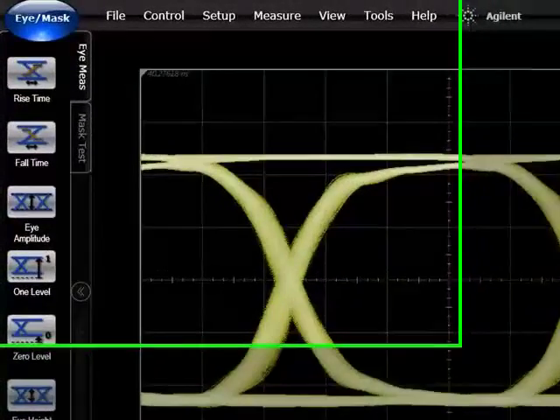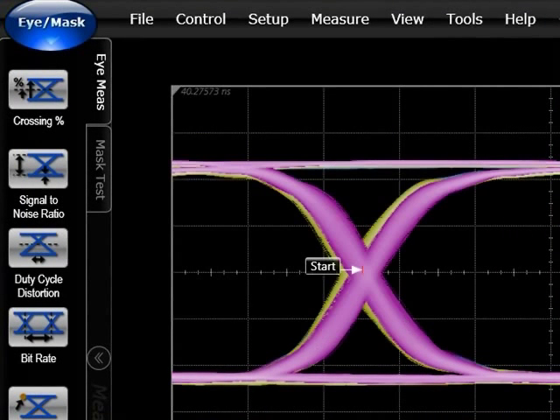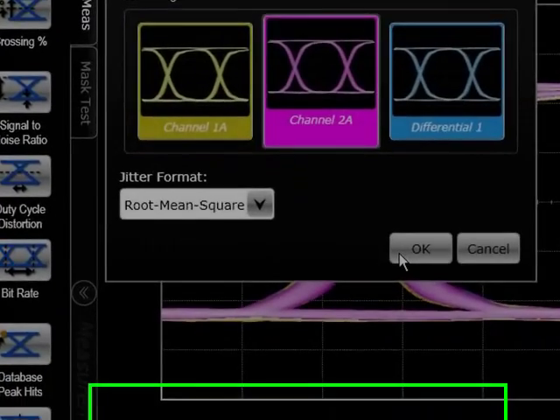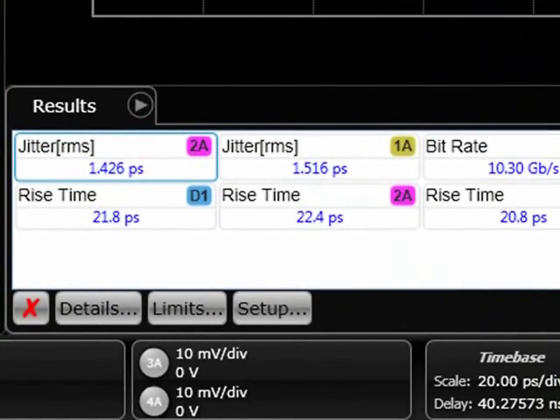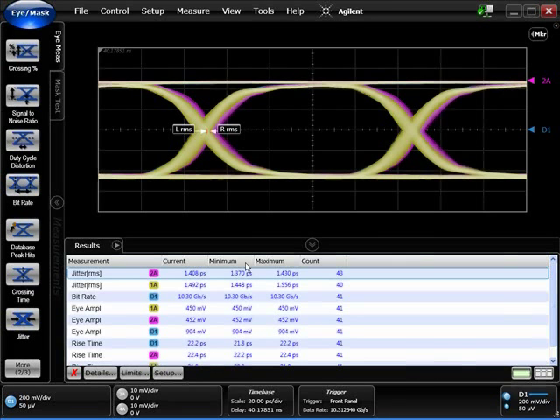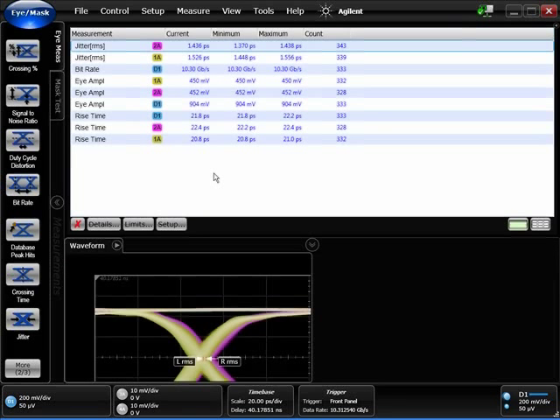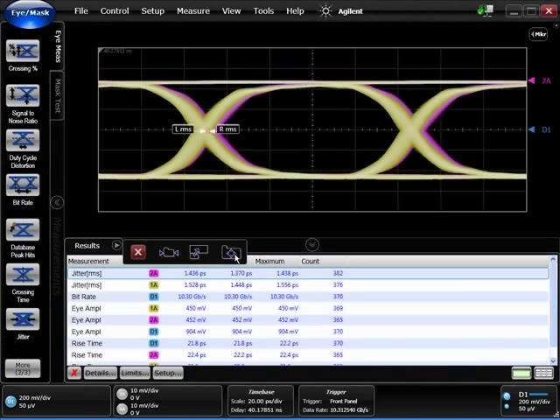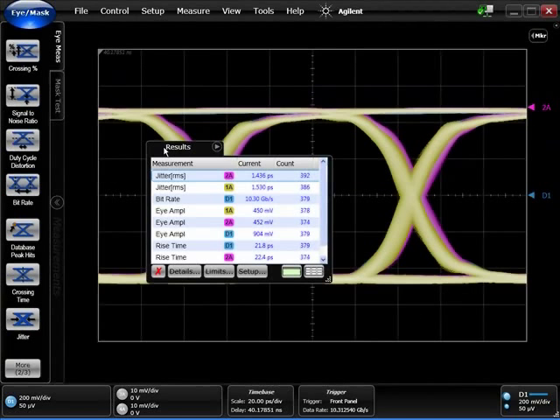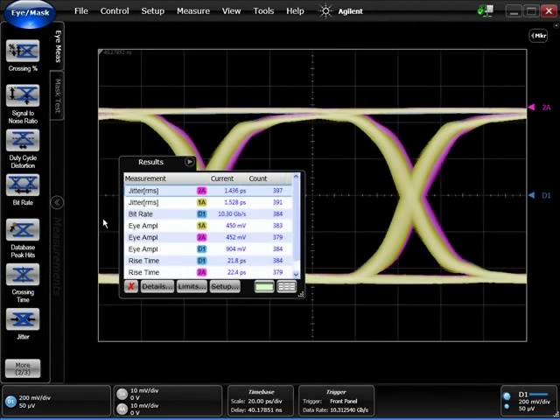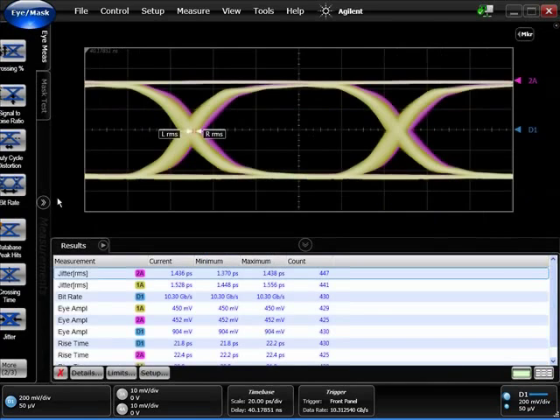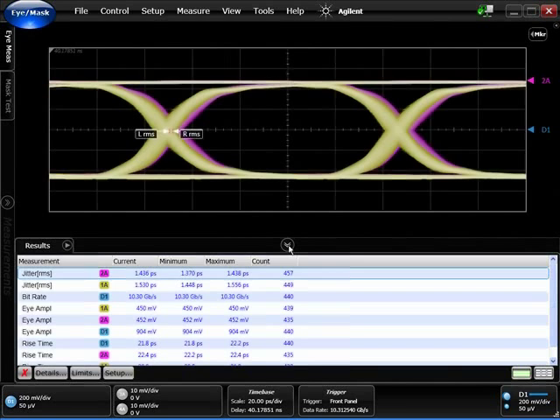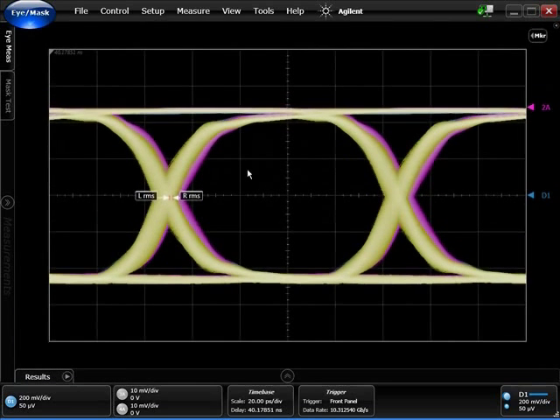Let's go ahead and turn on jitter measurements. While the DCA-J was limited to displaying up to four measurements simultaneously, the new FlexDCA software can display up to 64 measurements at the same time. If the measurements are what's most important to you, it's possible to drag the results tab up into the main window so your measurements are front and center. It's also possible to have windows floating, which is especially handy if you have a dual display. We can also maximize the main window by minimizing the icon tab on the left-hand side and minimizing the measurement tab, so the waveform is maximized.